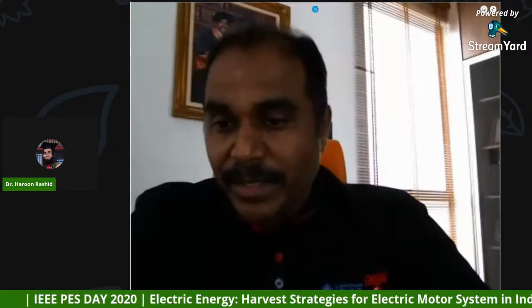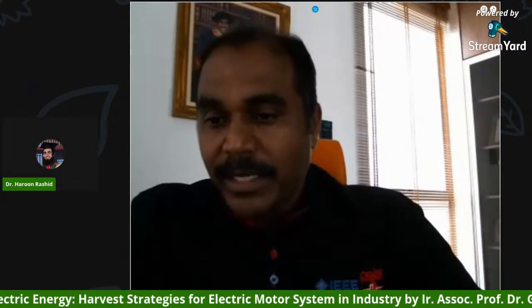But in this case, as you can see, the power factor is also very low, as you mentioned. Why is the power factor very low? Because the load is very light. When the load is very light, your power factor will be very low. That is another indication that your load is very light. Because it is very light, the VSD will control the voltage. As you control the frequency, the voltage will also be controlled automatically by the VFD, usually, because this V/F ratio will be maintained.